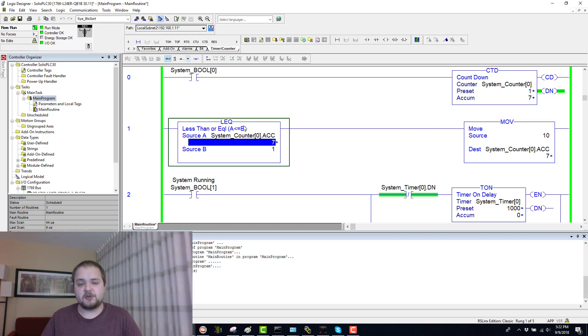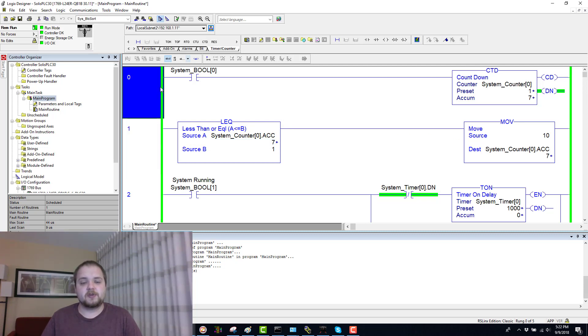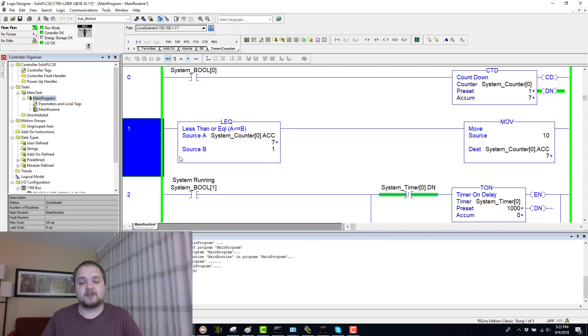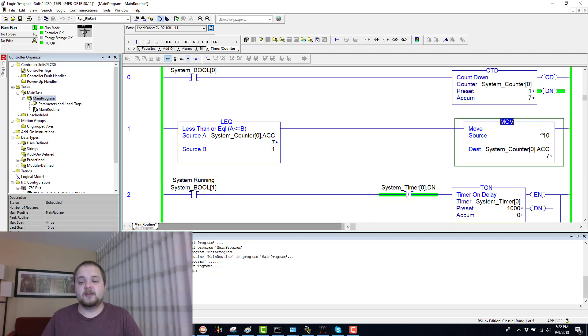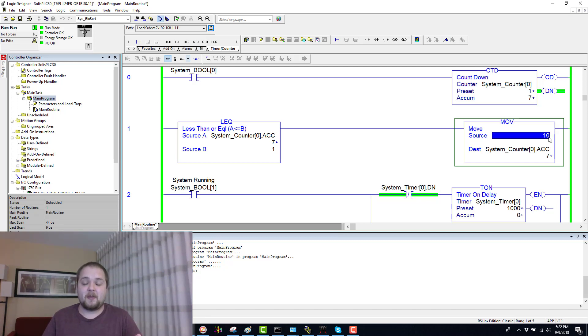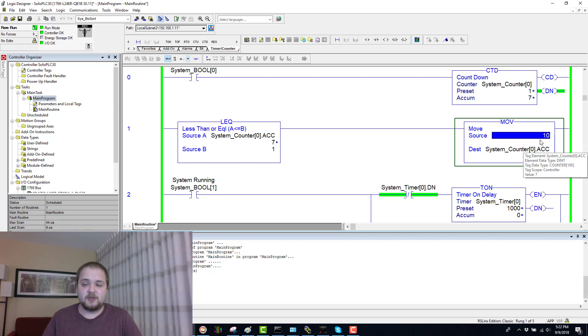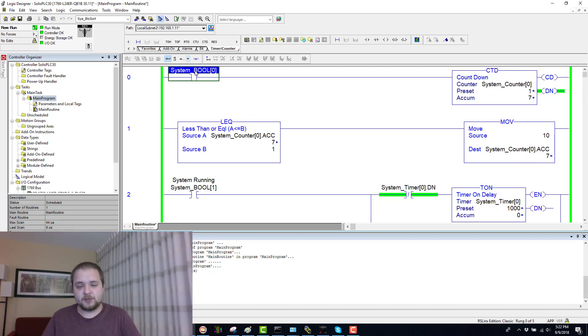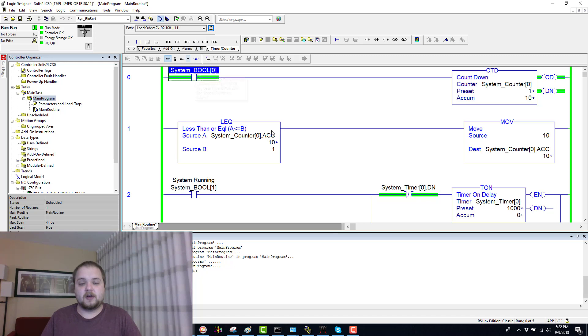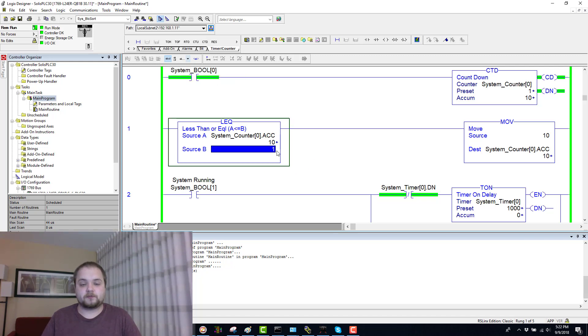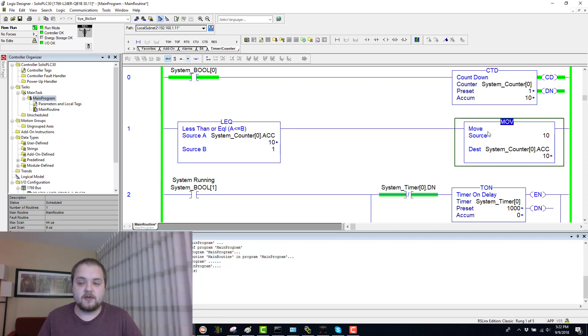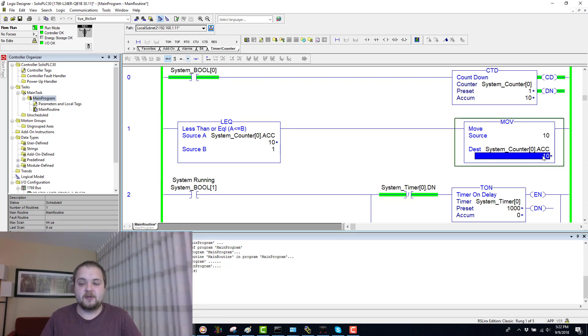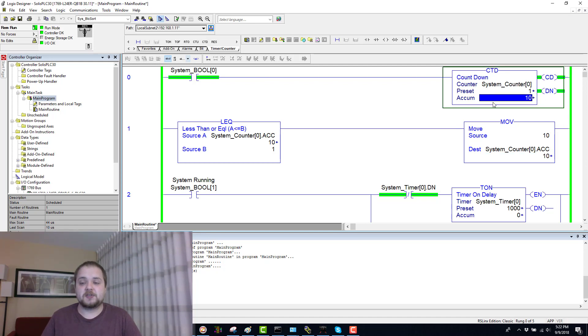What happens is, since the PLC continuously scans this logic, as soon as this accumulated value becomes zero, this move instruction is executed. What this move instruction does is essentially put this number, it puts this number 10, into the accumulated value. Observe what happens after I toggle this boolean back and forth. As you can see, we can reach less than one, or essentially we make this true, and then a move occurs and we move this 10 into the accumulated value of our counter.